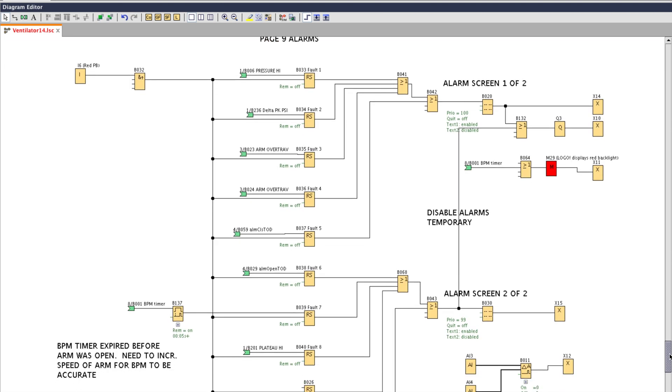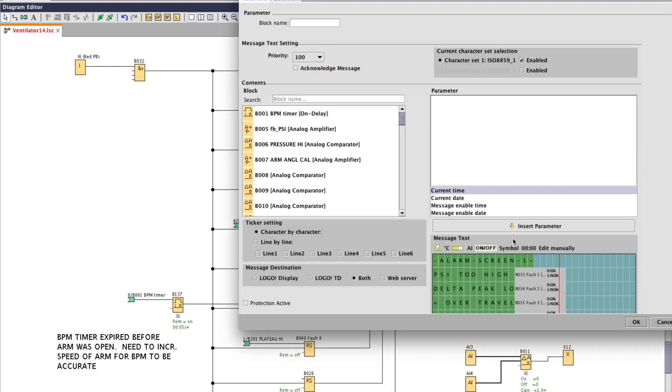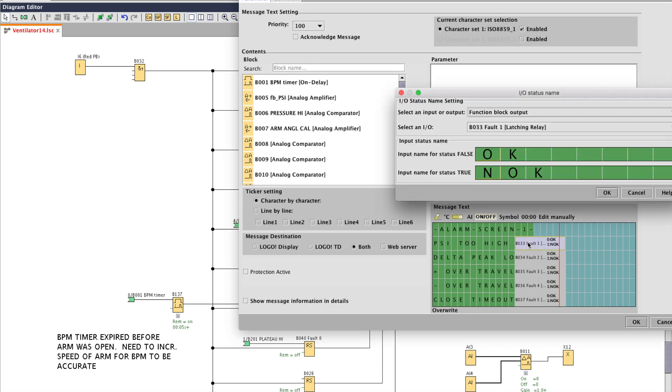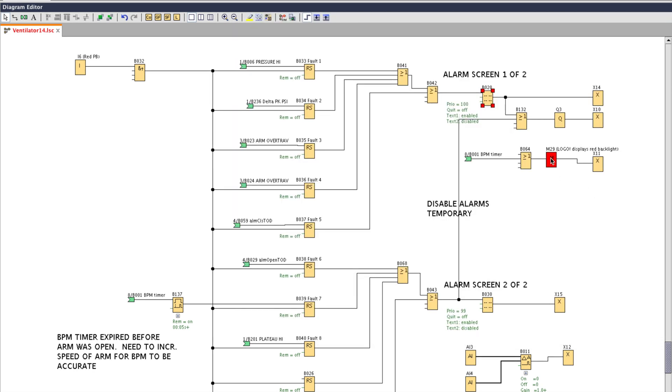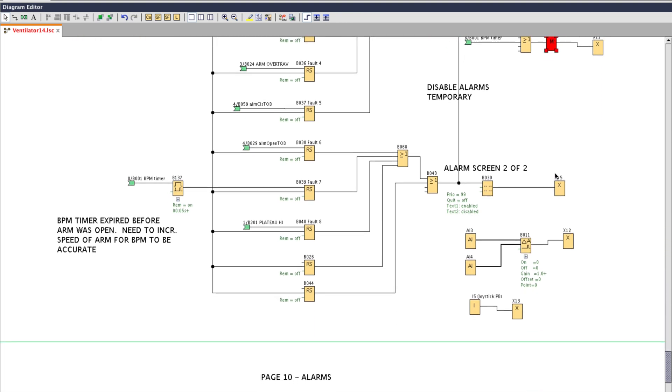This is the alarm screen. These are a list of all the alarms that we have and they latch a flip-flop. And if we press the red button that will unlatch the flip-flop to reset the alarms. This instruction I have highlighted is a message instruction and that's how we write information to the screen. In the gray box you can change the text displayed based on a boolean value. This red block is what changes the backlight color of the LCD. There's also white and orange.